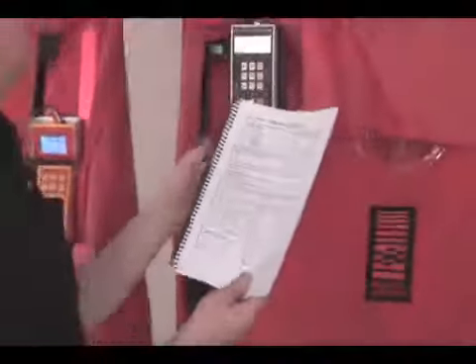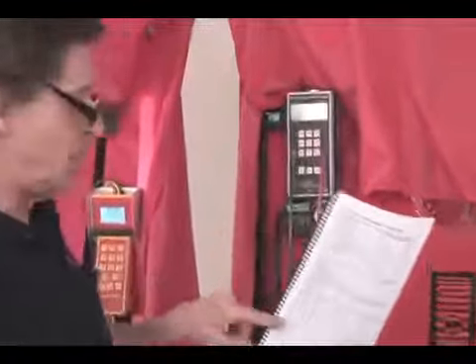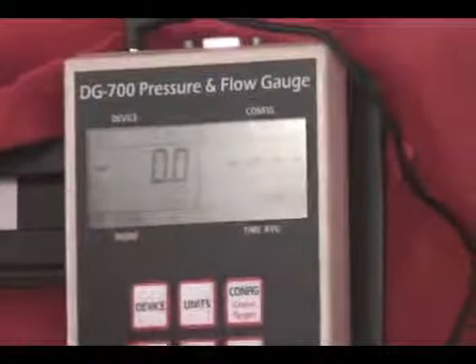There's a really common mistake that people make when they're doing that: they'll have the gauge set on 'at 50'. So let's see what happens if we take a set of readings from 15, 25, and 50 pascals, and see what kind of data we get if the 'at 50' setting is set.